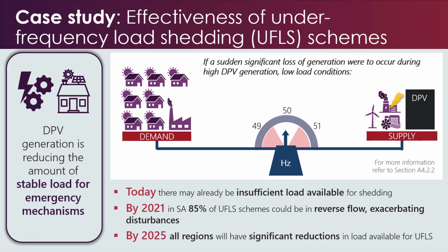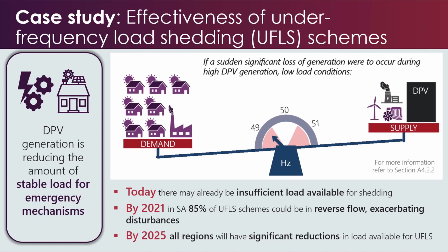Looking at the seesaw balance once again, as previously shown, these houses on the left have solar, but this is instead represented in the black box on the supply side. This scenario takes place during low load conditions but lots of DPV generating, such as in the middle of the day during a sunny, mild spring day. Following some unrelated but plausible reason, a generator may trip and disconnect. We can see this as the icon goes grey. The supply side becomes lighter and the scales tip. Frequency reduces into the red zone.